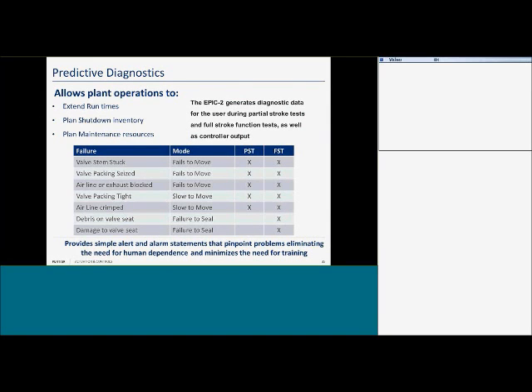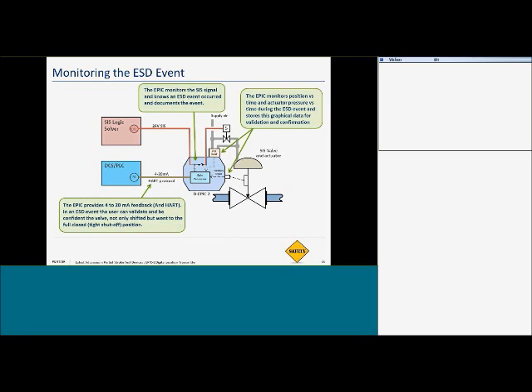Some of the diagnostics capabilities of that control device allows us to have some predictive maintenance rather than reactive maintenance. So we can predict that we're starting to develop some valve issues, potentially packing, torque increasing, crimped air line. This is very common. We start to see not enough air volume to stroke the valve correctly, seat failure, all kinds of issues can be diagnosed with the Digital Epic 2. And again, as I said, I'm not doing a training on this today, but this is something I would recommend that you put more effort into learning about if this is a product you're responsible for.